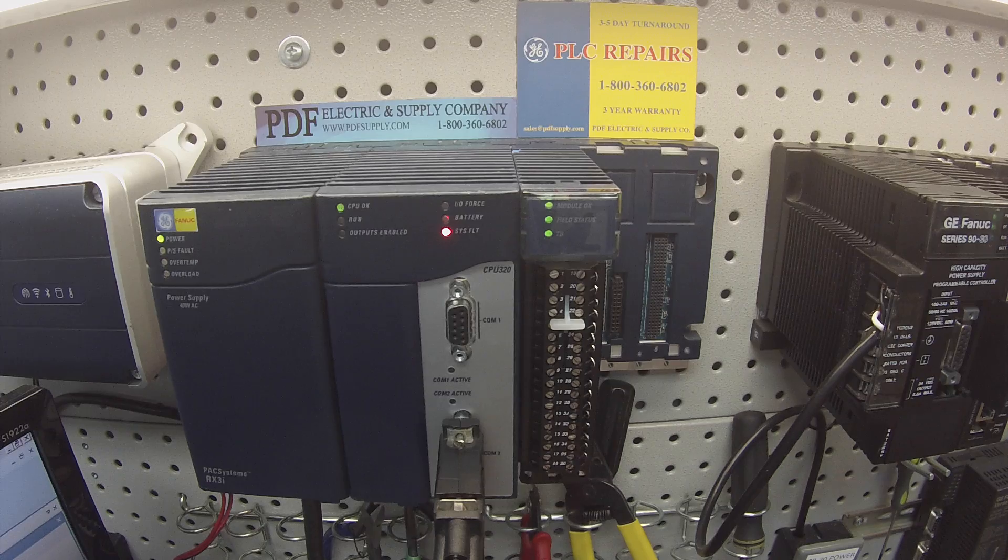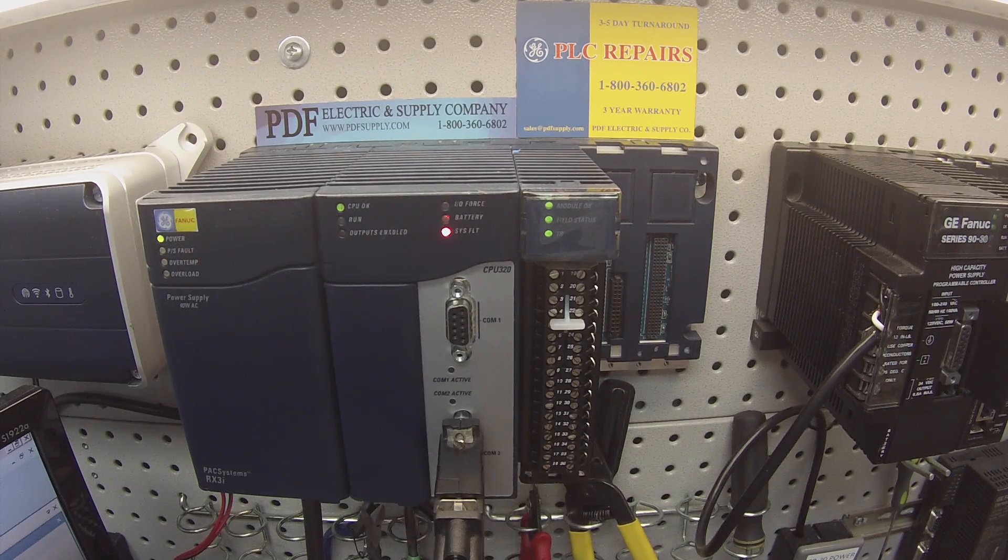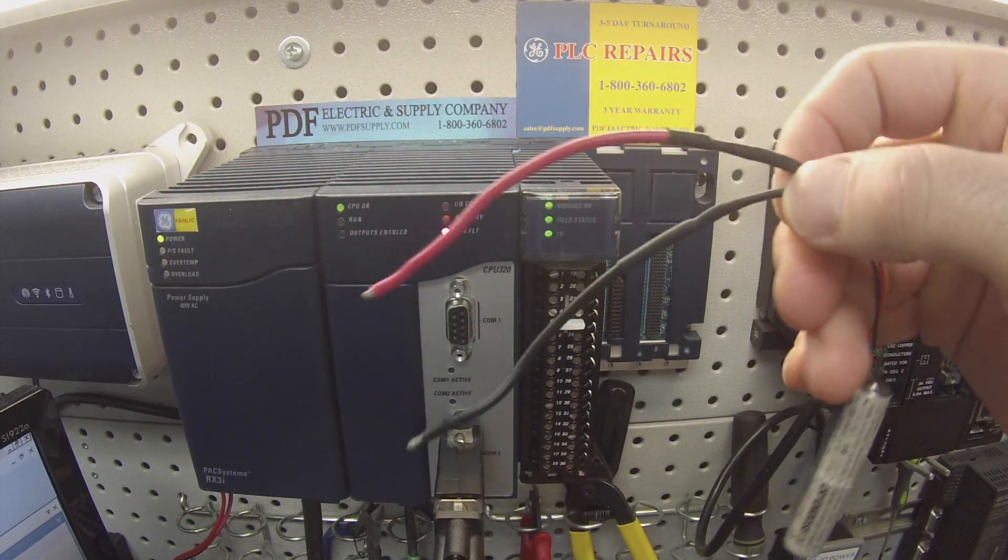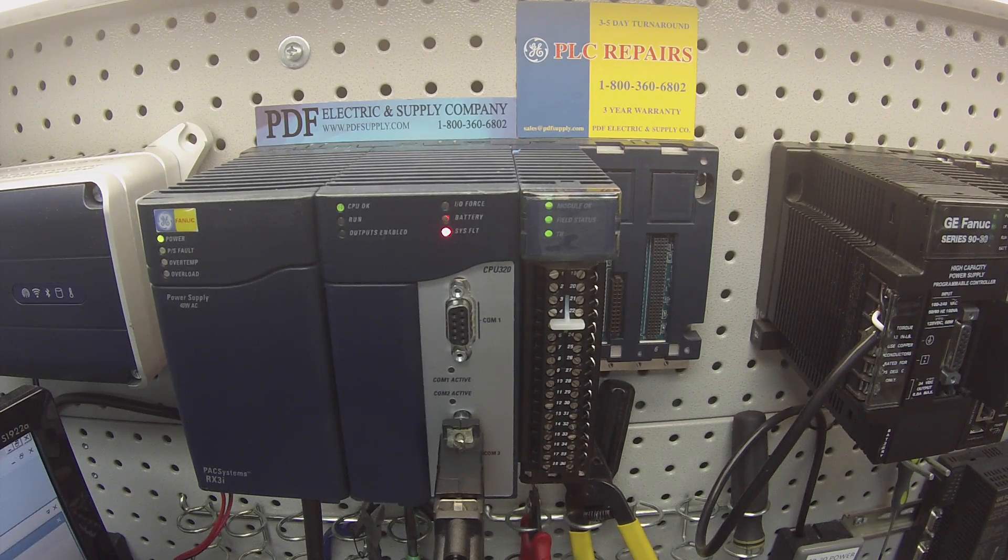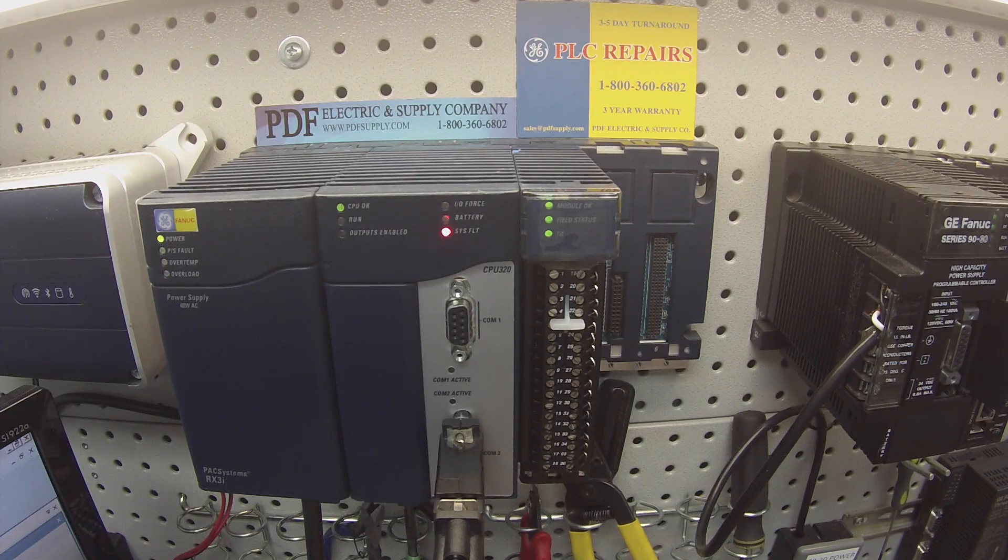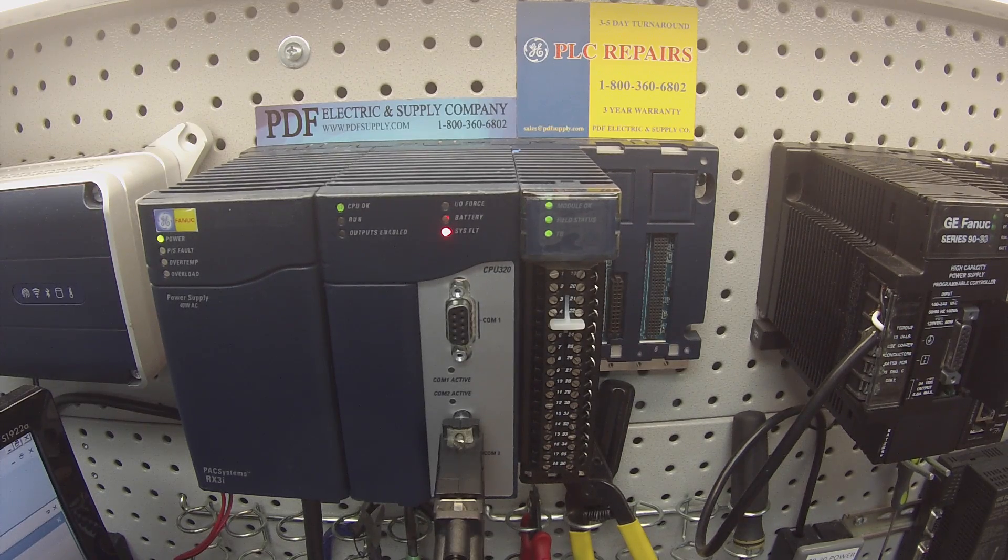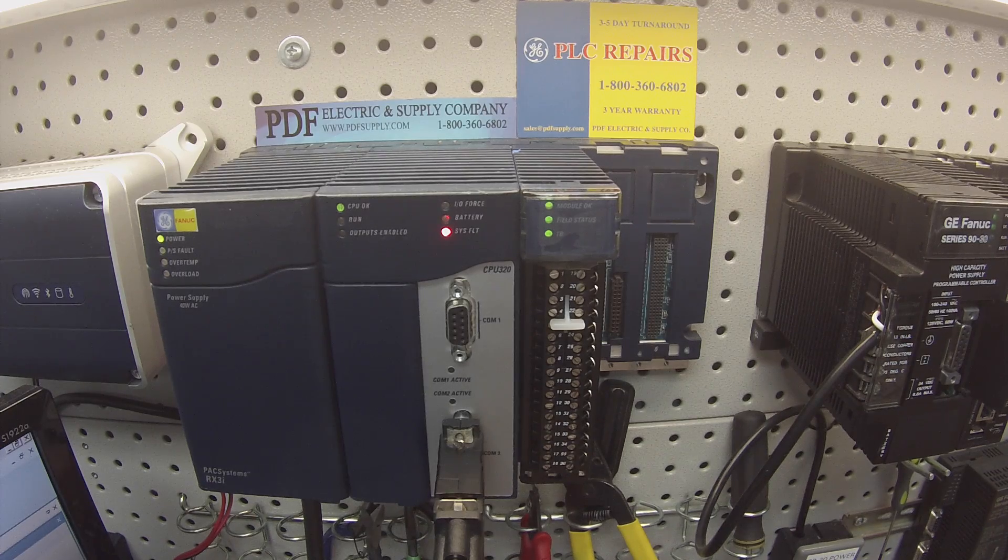Now that it's connected, the two devices I'm going to be using for this test are: for my voltage end, I'm going to use a three volt DC battery with a positive and negative lead attached to it to probe each channel. The other thing I'm going to use is a 4 to 20 milliamp output generator with adjustable range. It's 4 to 20 milliamps DC. That's important. I'll get into why the range and resolution is a very important thing to test in just a moment.